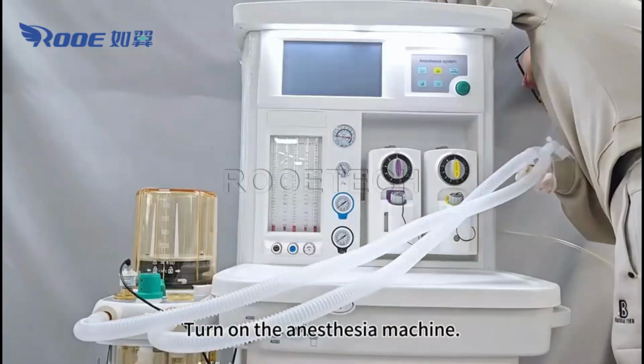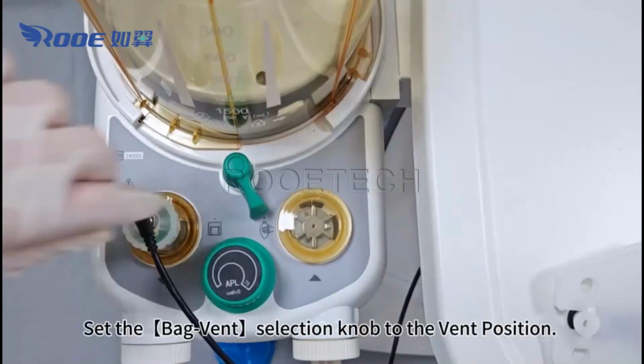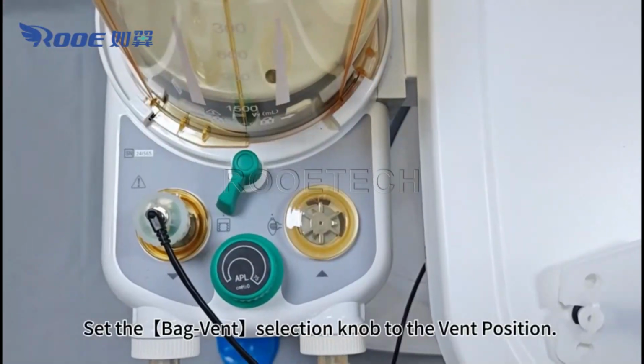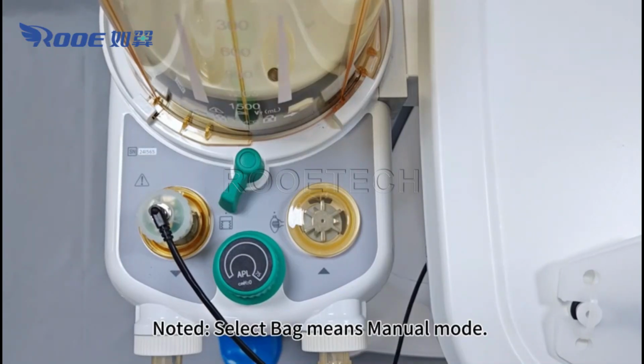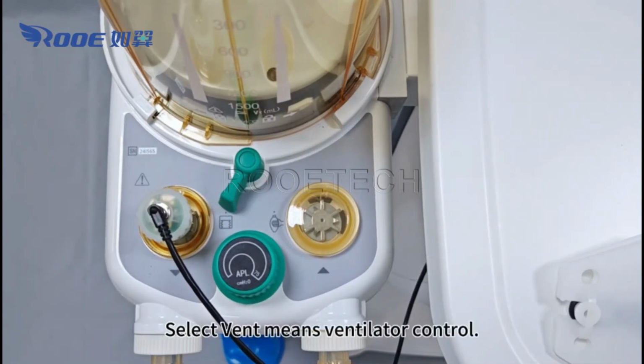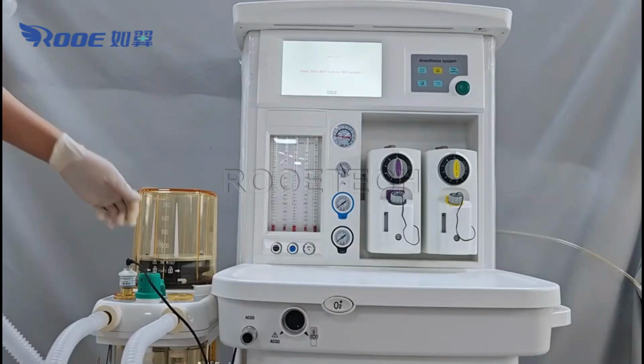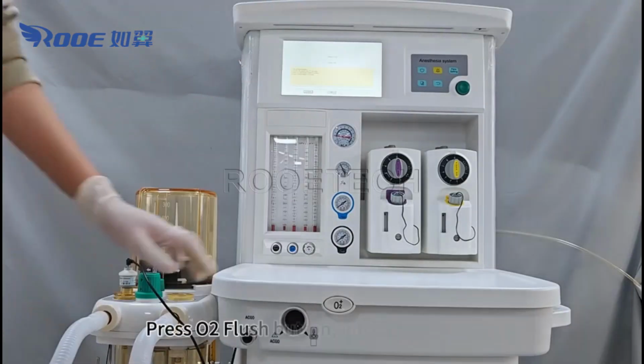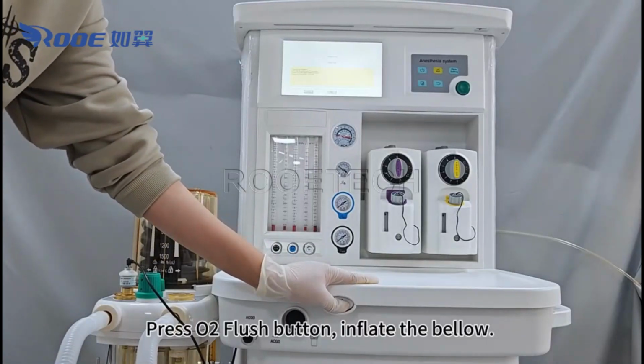Turn on the anesthesia machine. Set the bag vent selection knob to the vent position. Noted, select bag means manual mode. Select vent means ventilator control. It will enter self-test. First, sensor test. Press oxygen flush button, inflate the bellow.